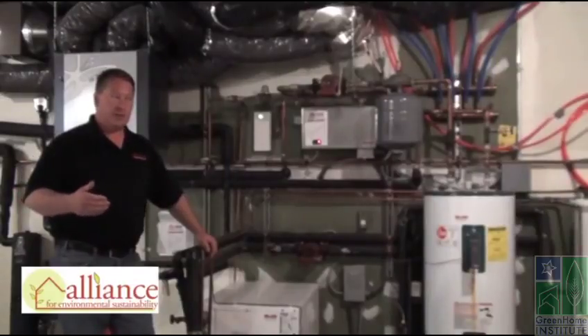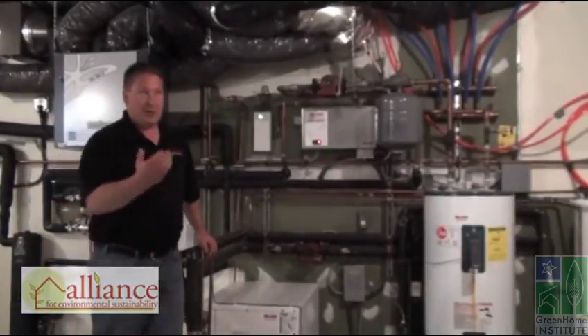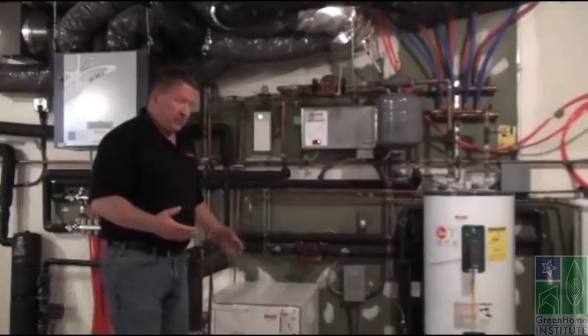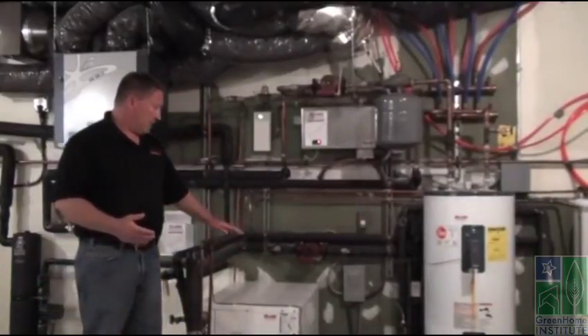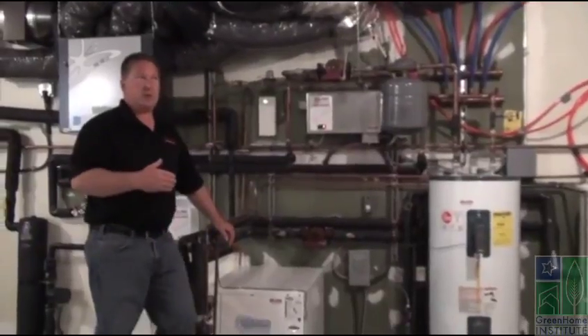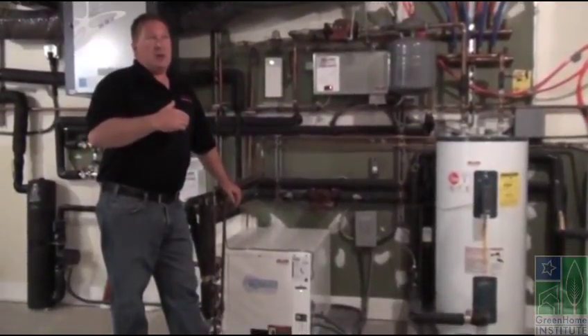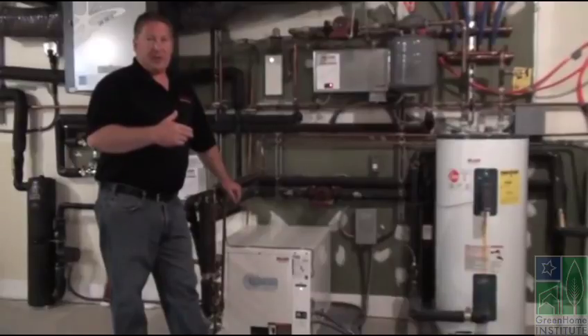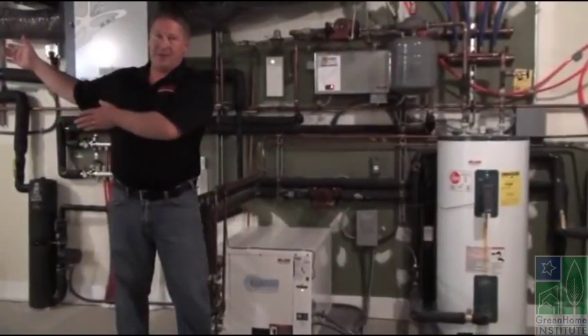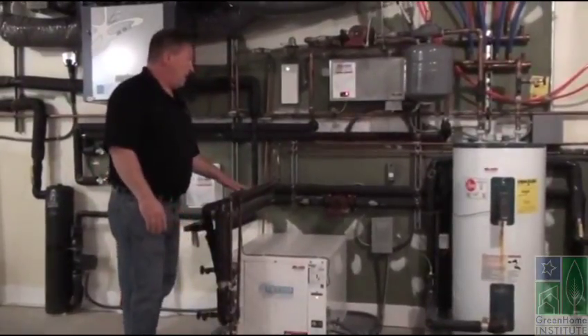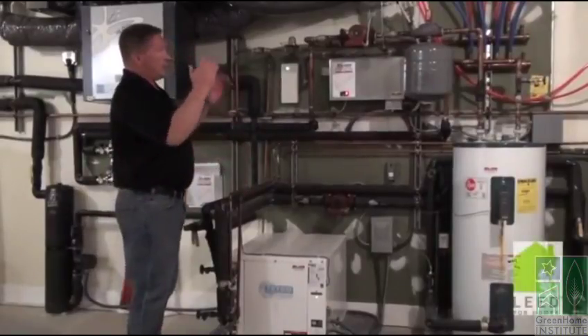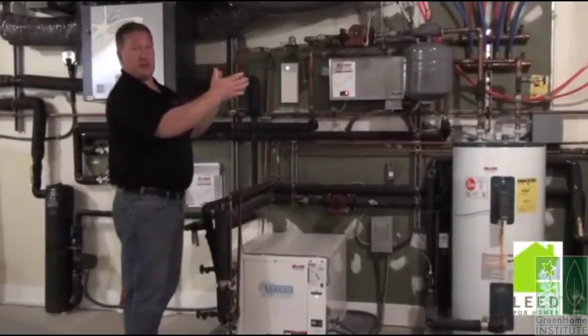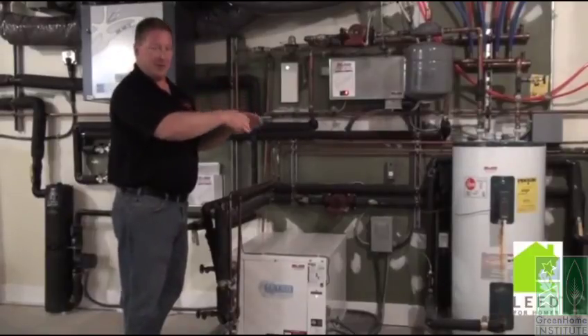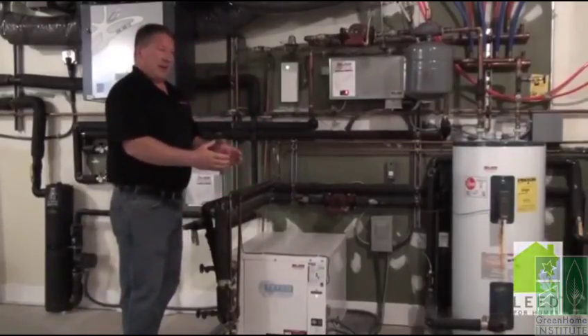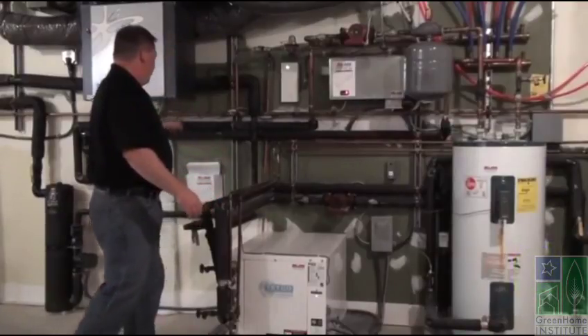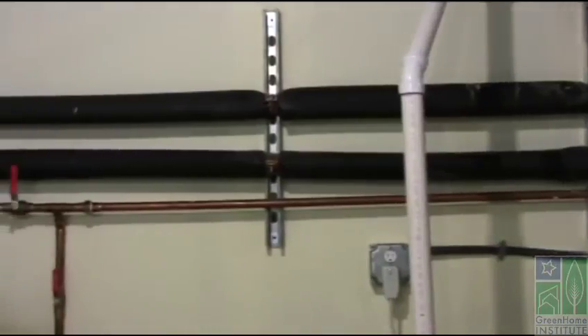It's just circulating water through that big thermal concrete mass, which is the house. In the cooling season, this has a reversing valve on it, and it reverses the direction or the path of refrigerant flow. So we can actually take the water that's coming in from outside, which again is separated by a heat exchanger, and circulate water in the floors and remove the heat that's built up in the floors into the water. It comes back to this unit, and that heat is removed or transferred into the water and piped outside and dumped into the earth.